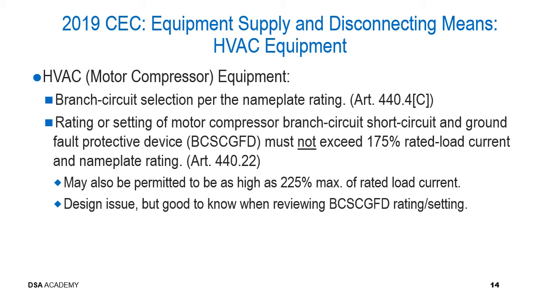Now again, there is an exception to this. It may also be permitted to be as high as 225% max of the rated load current of the motor compressor. Now we understand that this is basically a design issue, and that the capacities, the power, and the load of all equipment is going to be reviewed, determined, and verified by the design team. However, even though this is a design issue, it's good to know when you're reviewing the BCSCGFD ratings and settings that it is certainly acceptable if that particular rating is as high as 225% over the max rated load current.